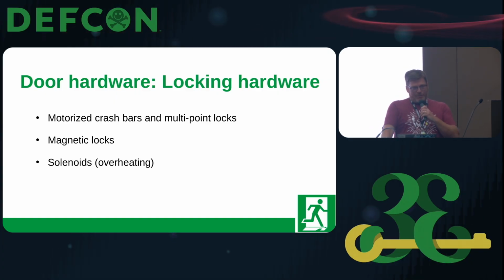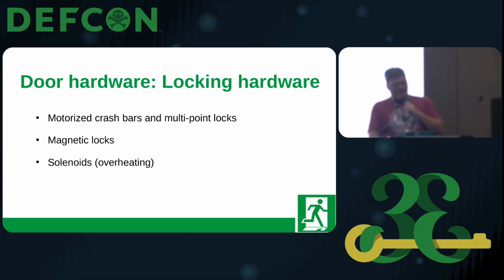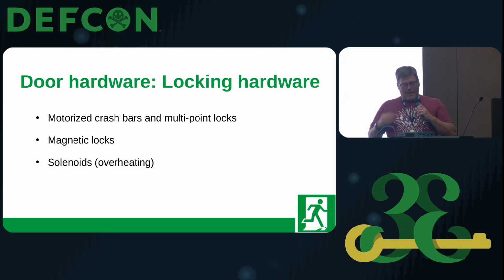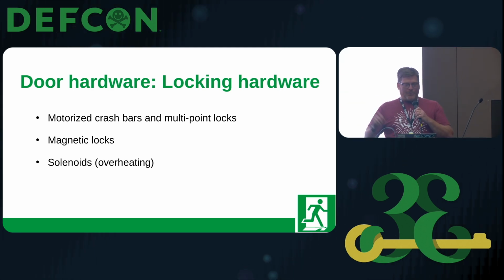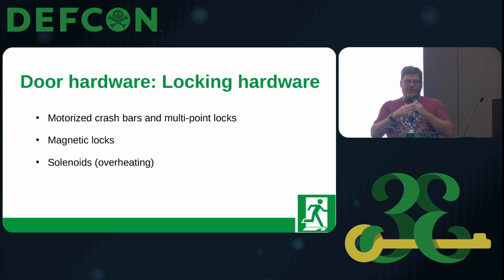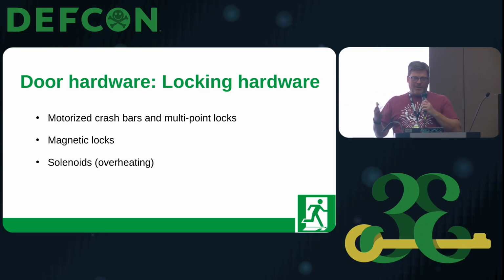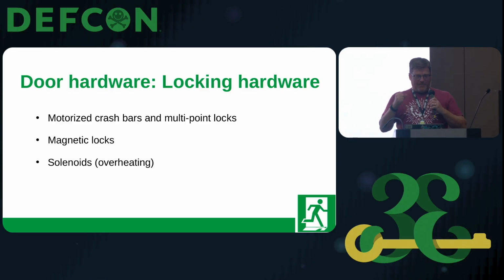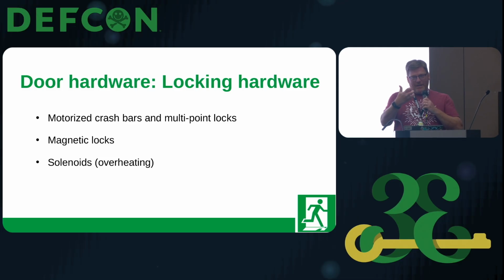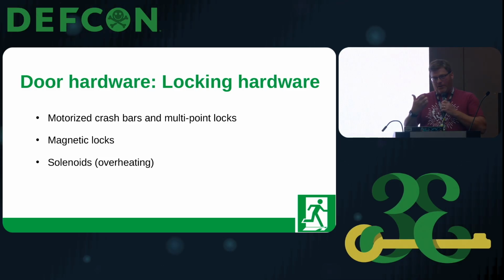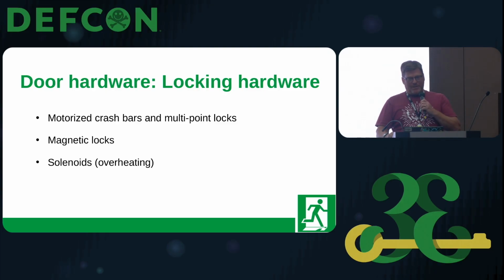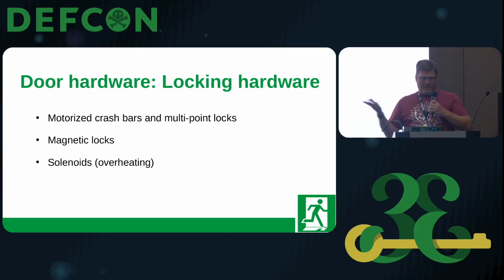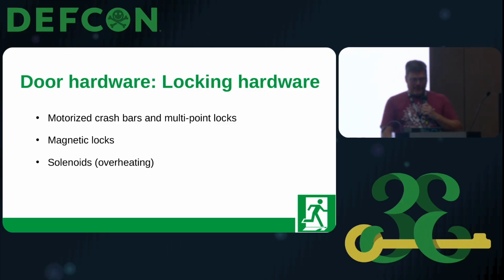And then any doors that have solenoids. I've seen this happen a few times, just standard solenoid unlocked doors. If this door is unlocked during business hours, 8 to 10 or 12 hours a day, you may notice that the handle feels warm. It's because that solenoid is constantly activated during business hours, and it can fail on you, and then you can't open the door at all. So it's just something to keep an eye out for, and make sure you have something that is better suited for that particular door.